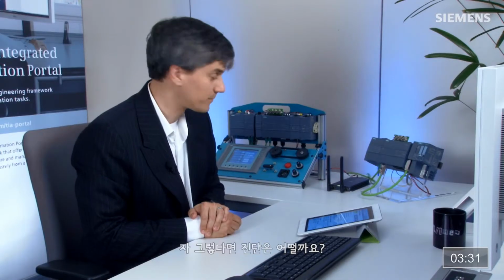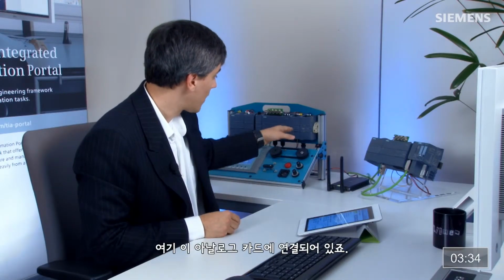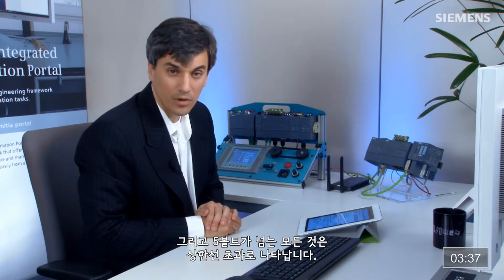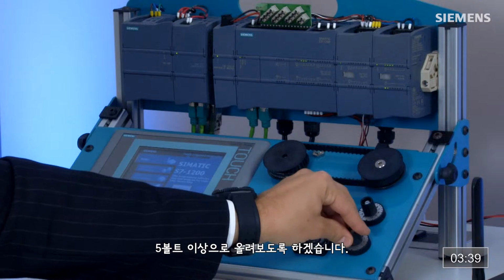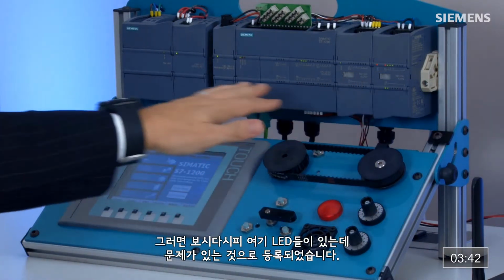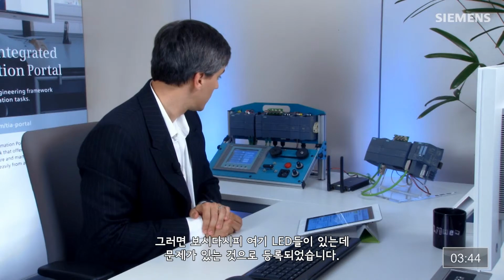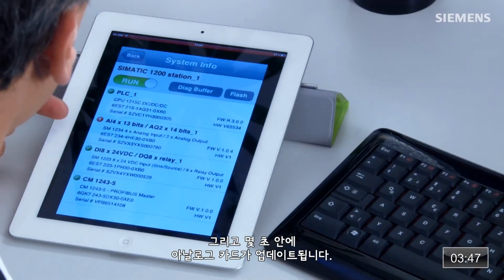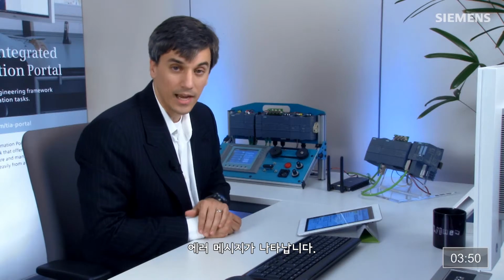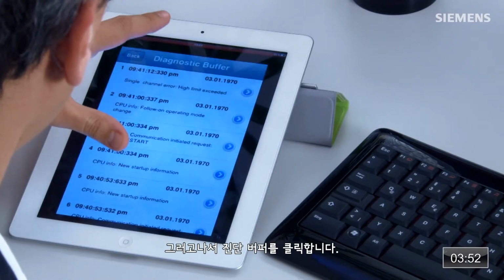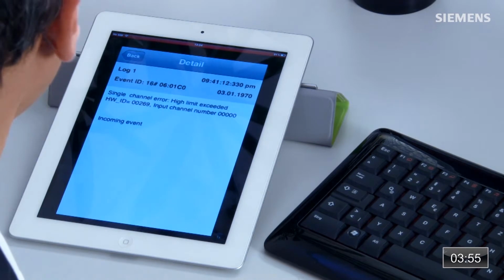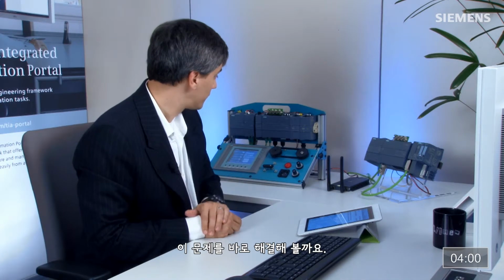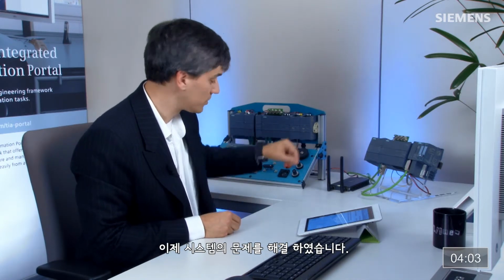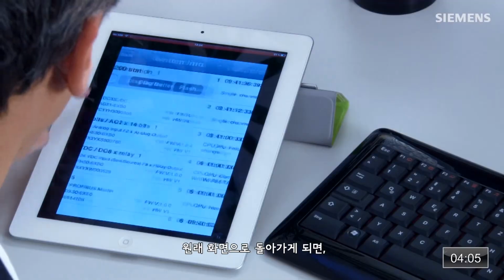OK, how about diagnostics? Currently I have the potentiometer wired into this analog card, and anything above 5 volts is going to be high limit exceeded. So let me just turn that above 5 volts. Now you can see the LEDs across here. We do have the registered fault at this point, and the analog card will update here in a few seconds. Now it has, so there is an error message with it. And they click on the diagnostic buffer. First message, single channel error, high limit exceeded. That is exactly correct. Let me solve the problem real quick. Now the control system has solved the problem, and if we go back to the original screen, there's absolutely no problem with this analog card either at this point.